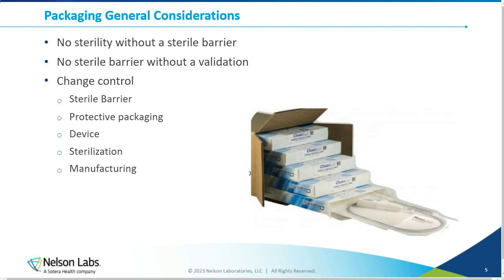When we're looking at making changes to the packaging system, and again, that's anything in this picture, not just your pouch, you've got to have good change control procedures in place. And those change control procedures need to look at the holistic picture, not just the sterile barrier, but also the protective packaging. Look at the device. And maybe you're changing sterilization, as we're talking about here. How does changing sterilization affect the packaging system? Maybe you're making a manufacturing change and you might not think that would affect the packaging, but it can.